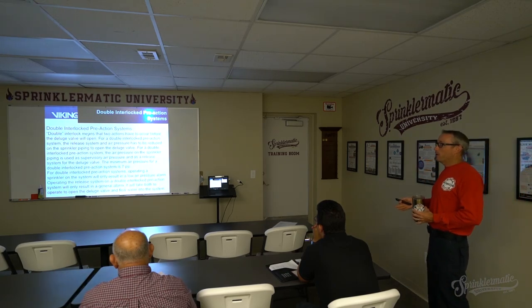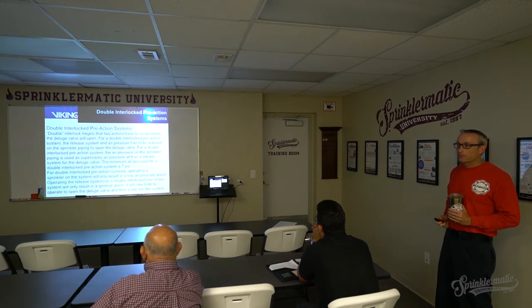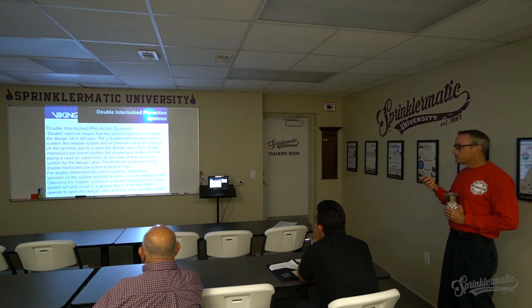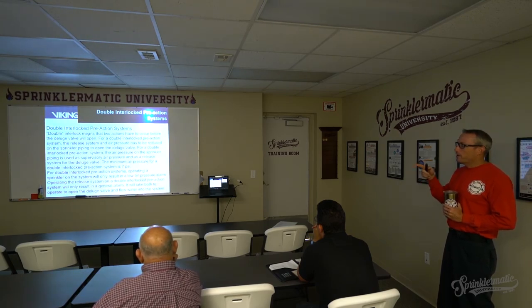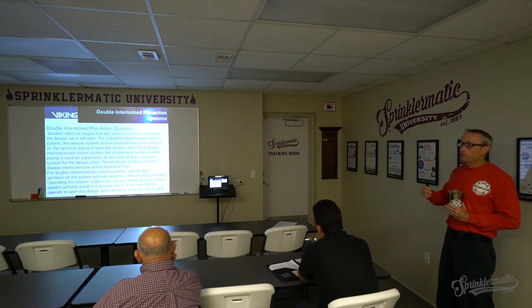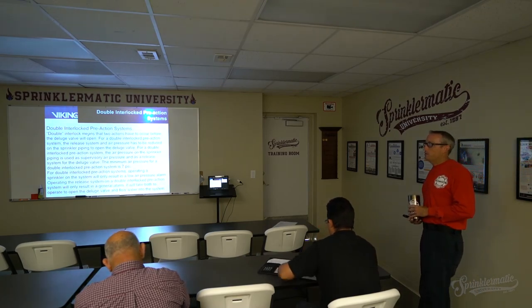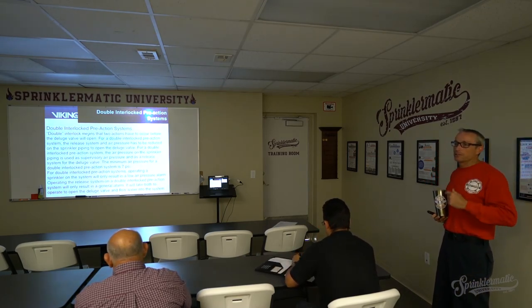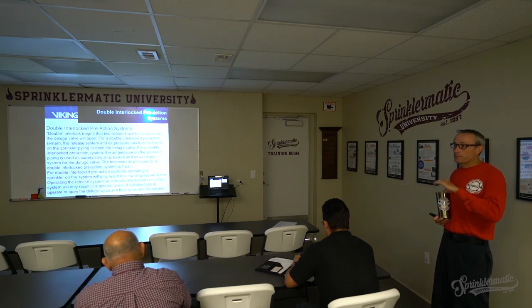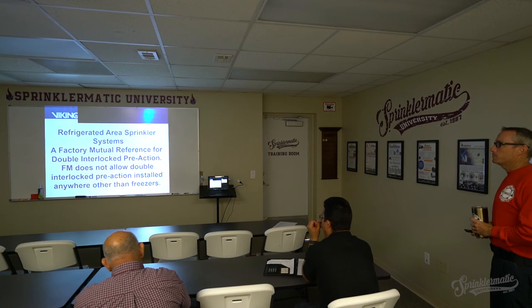So double interlock preaction systems are installed in places where you are really, really concerned about accidental water damage. The reason why these aren't as prevalently installed as the single interlock is because of that two-action response. It doesn't act as close to a wet system as that single interlock does. The single interlock preaction system is very similar to a wet system, because once the detectors operate, the valve is tripped and water is in the pipes ready to go when that sprinkler head breaks, which in the double interlock, it's still not. Does that make sense?